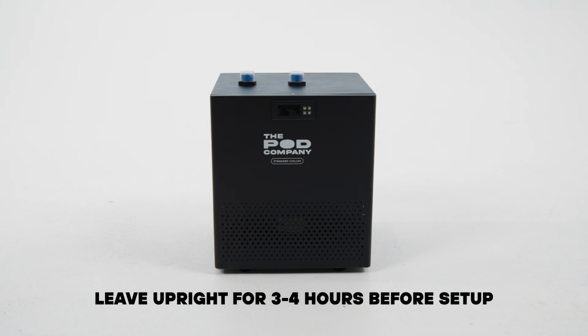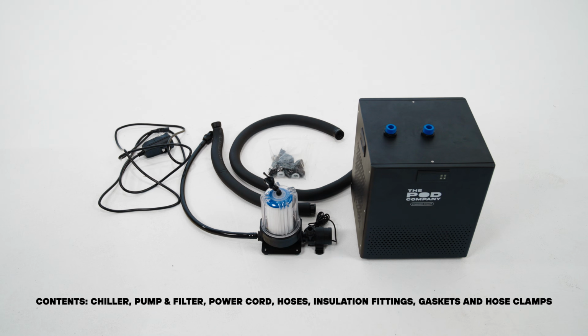Before you begin setup, it's crucial to let the chiller stand upright for 3 to 4 hours to allow the internal fluids to settle after transport. This prevents malfunctions. Let's check what comes in the box. 1 water chiller unit, a 9-foot power cable with a safety button, a water filter and pump unit, hoses of different sizes with pre-installed insulation, fittings, gaskets, and lastly, hose clamps.